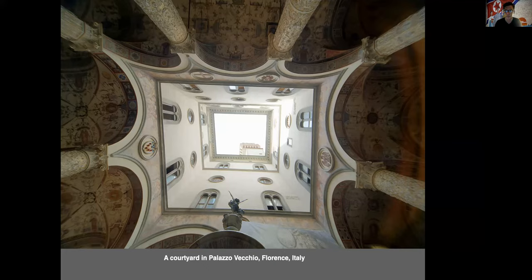The fountain is directly underneath this opening in the courtyard. And so at nighttime, it draws out cool air and cools the entire building down. The mass of the building, the structure and material of the building, holds the cold air pulled in at night, and actually works as a sort of iceberg, so to speak, that during the daytime releases coolness through the evaporative cooling, through the draft that goes up to the top.